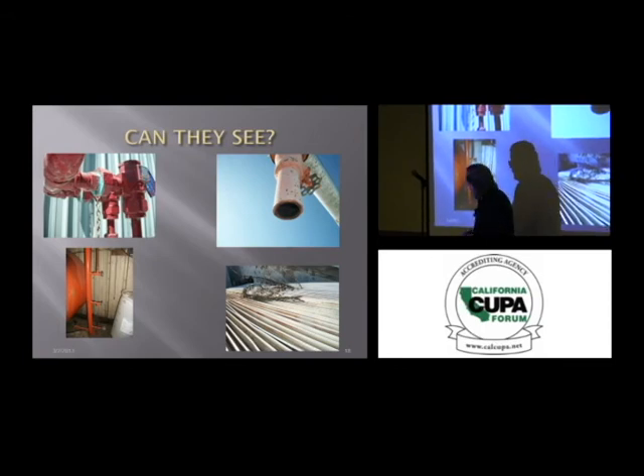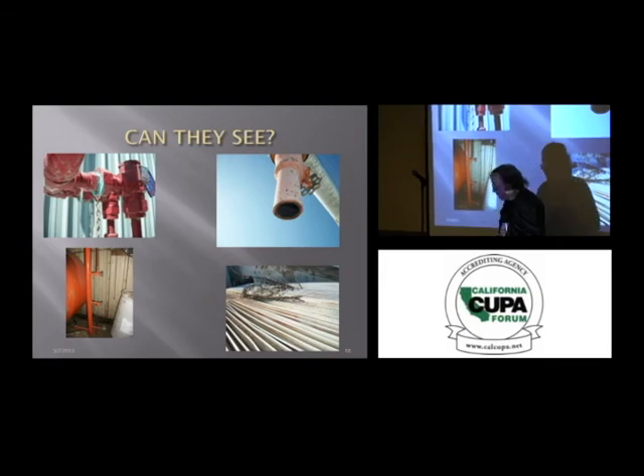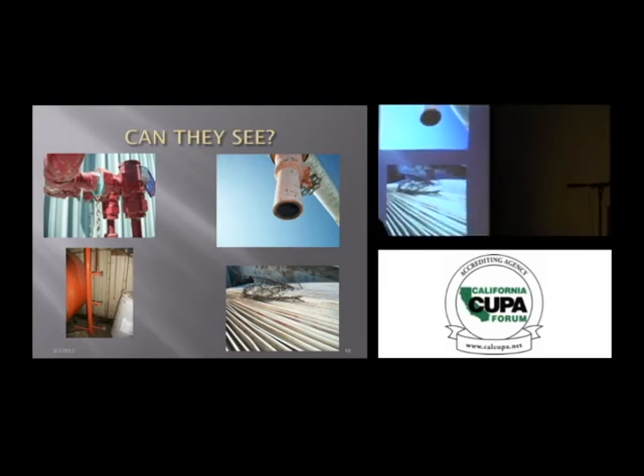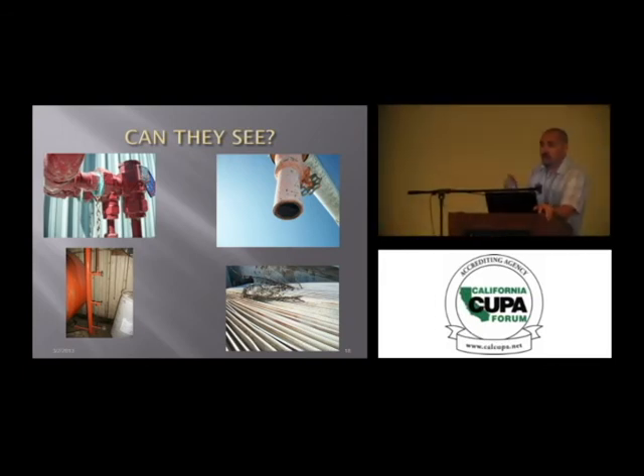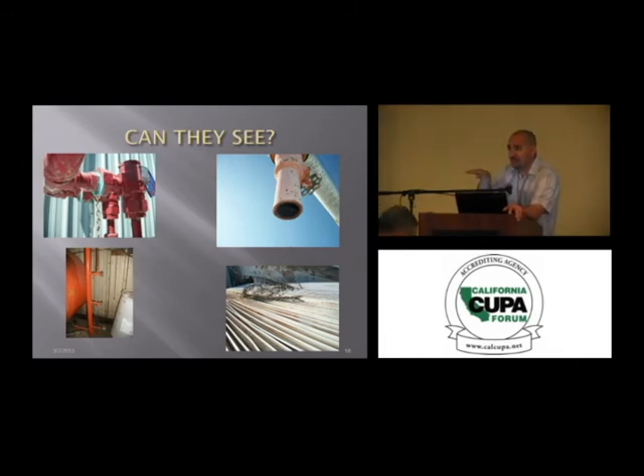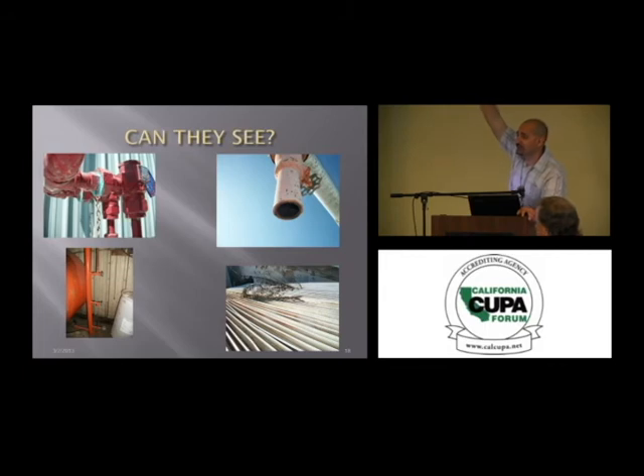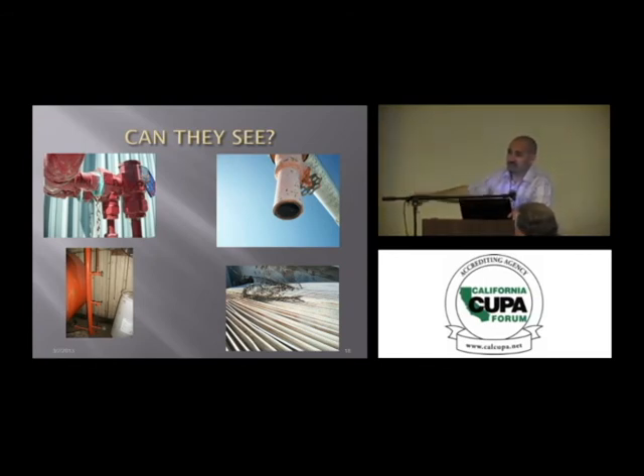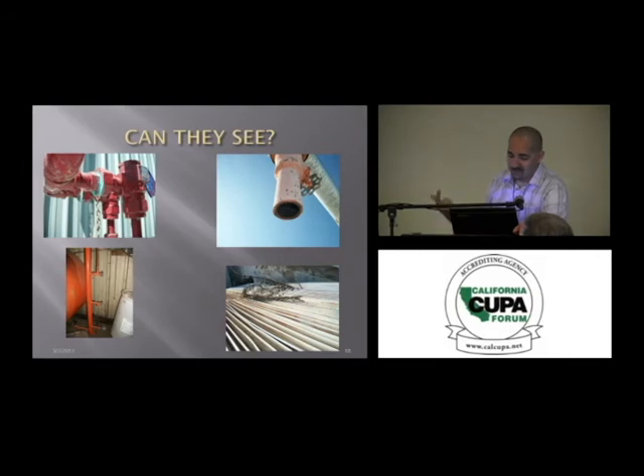Okay? Mike, can you point out that little 1/4-inch drain valve down at the bottom? This one right here? That little 1/4-inch drain valve is an easy one, I've replaced them myself, where it's a 1/4-inch nipple and the nipple's bent because somebody stepped on it, used it as a ladder to reach up and do something up here. That valve should always be protected. It should always have some sort of a guard, because once that valve breaks, you're going to have a heck of a time trying to get back under there and isolating. You can see the isolation valve on the bottom. You're going to have a hard time isolating that valve.